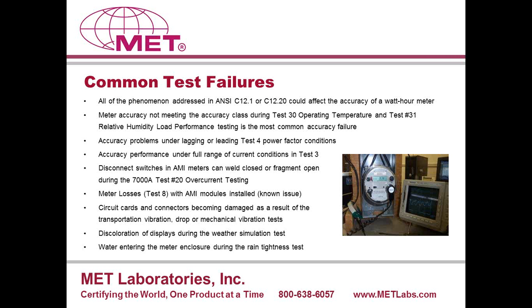Weather simulation tests are done for simulating UV and rain events or spraying events that are performed on the meter, and there we see occasionally discoloration of displays, discoloration of the domes, or even the plastic facing of the meter. Those are non-compliances.